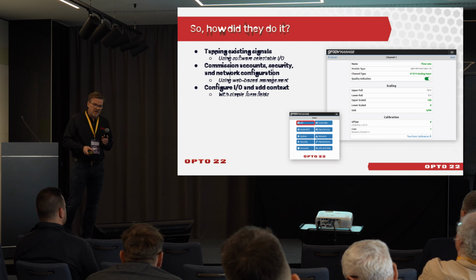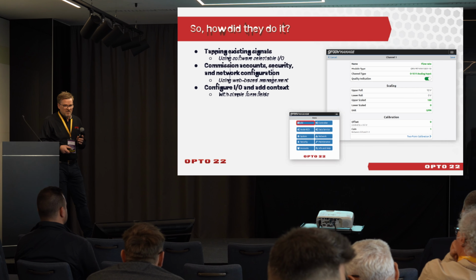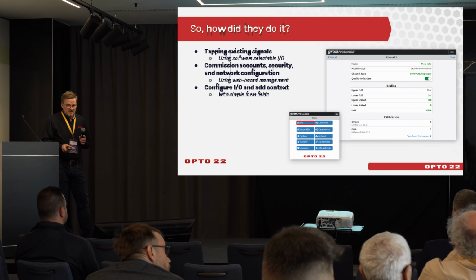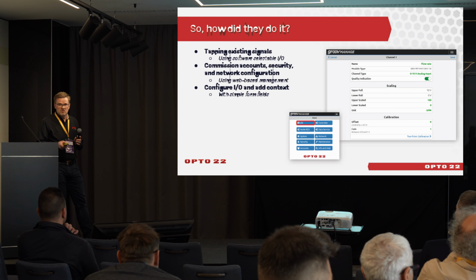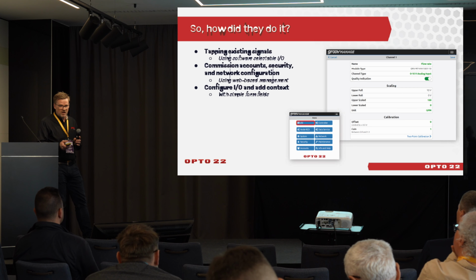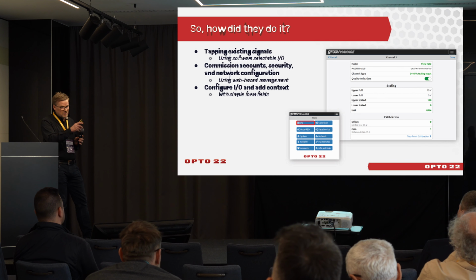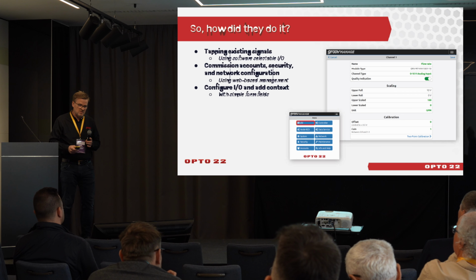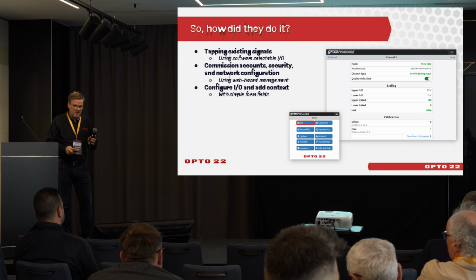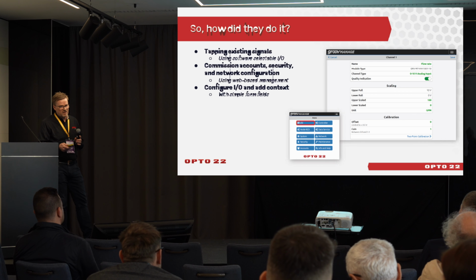Next, they configure the I/O points. Here's where they name the I/O points, which, by the way, is the single source of truth for the tag throughout the whole ecosystem. So the name you use here will be shown across your complete ecosystem. This is also where they set up other parameters like scaling and engineering units — again, just fill out the forms, check some boxes, and you're ready to go.